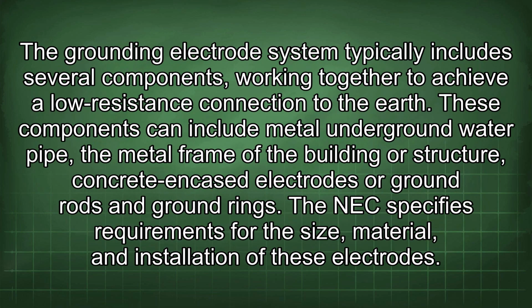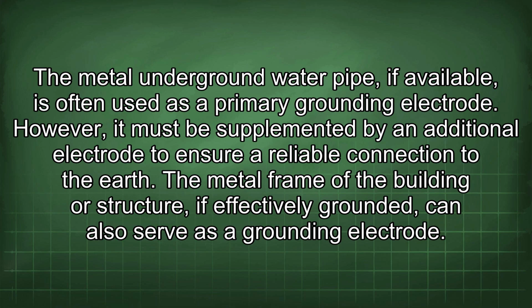The grounding electrode system typically includes several components working together to achieve a low resistance connection to the earth. These components can include metal underground water pipe, the metal frame of the building or structure, concrete encased electrodes, or ground rods and ground rings. The NEC specifies requirements for the size, material, and installation of these electrodes. The metal underground water pipe, if available, is often used as a primary grounding electrode. However, it must be supplemented by an additional electrode to ensure a reliable connection to the earth.